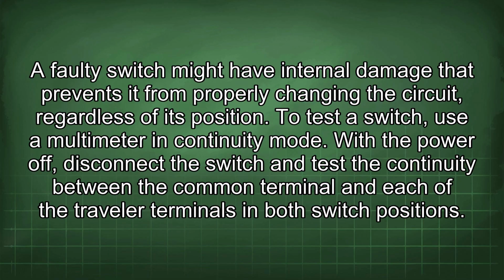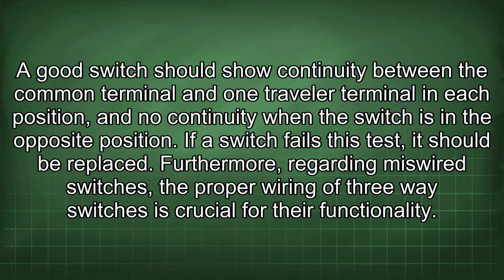To test the switch, use a multimeter in continuity mode. With the power off, disconnect the switch and test the continuity between the common terminal and each of the traveler terminals in both switch positions. A good switch should show continuity between the common terminal and one traveler terminal in each position, and no continuity when the switch is in the opposite position. If a switch fails this test, it should be replaced.